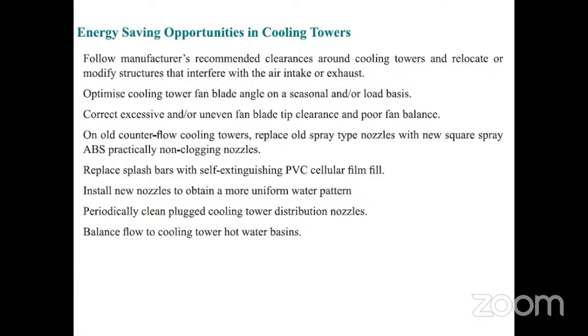Counterflow cooling towers: replace old spray nozzles with the new square spray ABS, practically non-clogging nozzles. All these types, just have it in mind, sir. I don't know practically what ABS non-clogging nozzles are. I don't have any idea. Replace the splash bars with self-extinguishing PVC cellular film, which is more effective than the splash bars, sir. That is being told everywhere in the book. Film is more effective than the conventional type. New nozzles to obtain uniform water pattern.